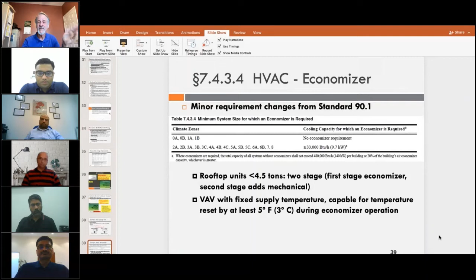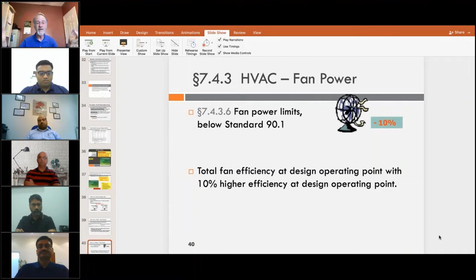But here's one that is interesting to look at. Fan power. Standard 90.1 has included for a number of years a maximum fan power based upon either the flow rate or just a rated power for the motor that's connected to the fan for a certain type and size of system. And at least I know a lot of people that have done duct designs can always do better. Standard 90.1 is sort of a minimum level, and we can do better than that. So what Standard 189.1, the International Green Construction Code, says is you do 10% better than that. And it's fairly easy to achieve. When I do these talks on a larger basis, over a longer time frame, I talk about all it takes to achieve that. It's not very hard to achieve.